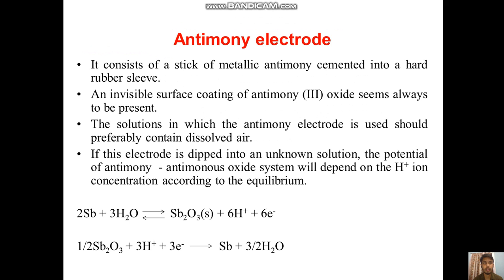The next electrode is the antimony electrode. It consists of a stick of metallic antimony cemented into a hard rubber sleeve, and an invisible surface coating of antimony oxide is always present. The solution in which the antimony electrode is used should preferably contain dissolved air. When dipped into an unknown solution, the potential of the antimony/antimony oxide system depends on hydrogen ion concentration according to a specific equilibrium.